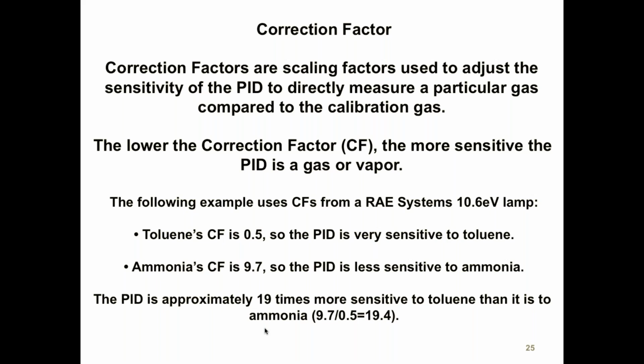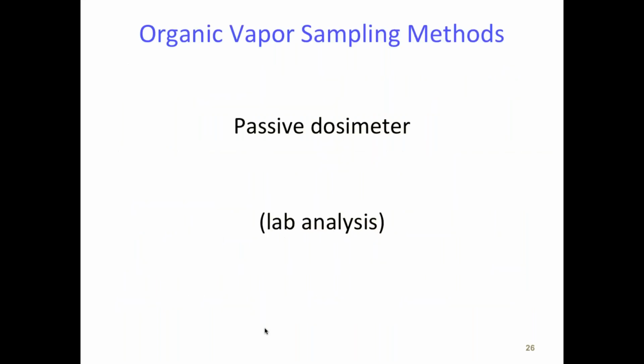It's going to interfere with the reading, and if that happens, then you have to take a little bit of solvent. You have to put your gloves on. They give you little finger cuts to protect your fingers from the solvent. You have to get your Q-tips out and clean the sensor off. It's a real hassle, right? So that's why you want to avoid getting that sensor dirty. So typically, when you use this, you would want to connect this simple filter to it.